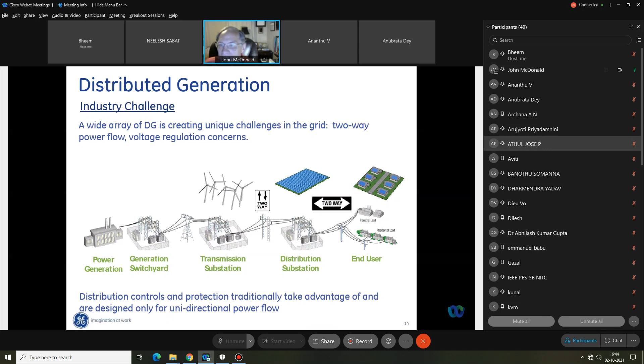So some of the challenges are open circuit overvoltage due to unintentional islanding, and protection ratings that may not match fault currents. As a protection engineer, when we need to determine the protective relay settings, we will do a short circuit study. We'll model the grid and simulate faults occurring to determine what the magnitude of the fault current would be at different parts of the grid, so we know what the protection rating should be.